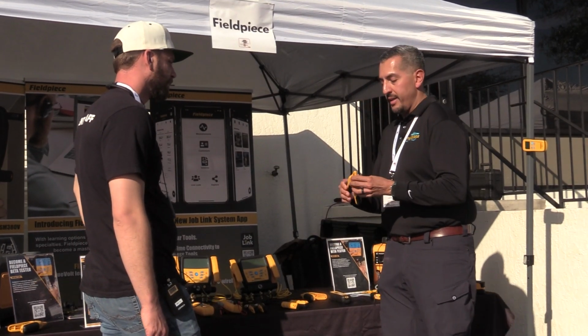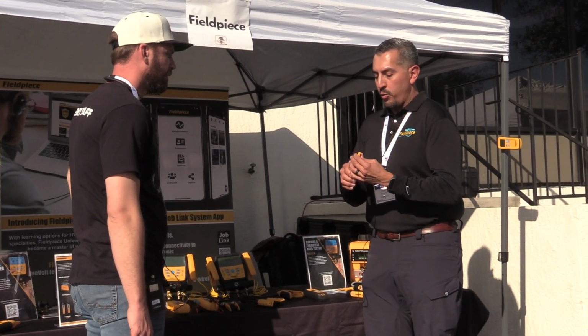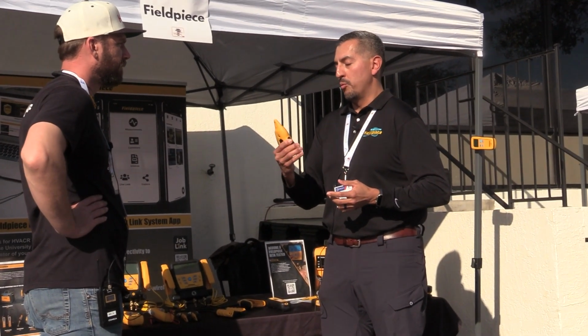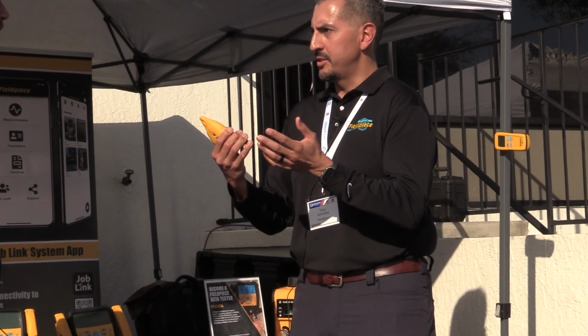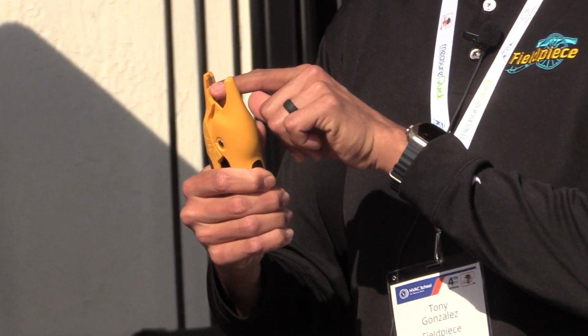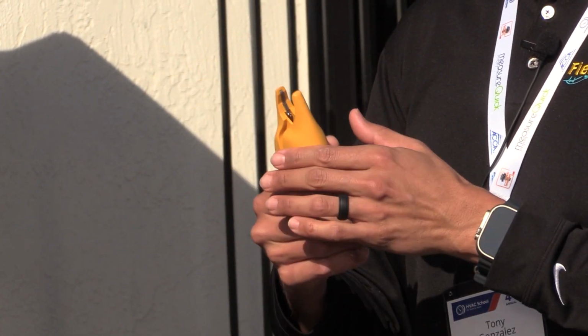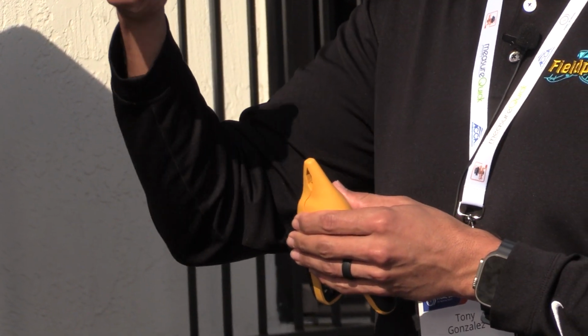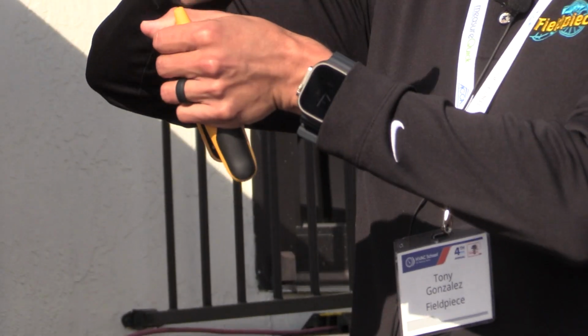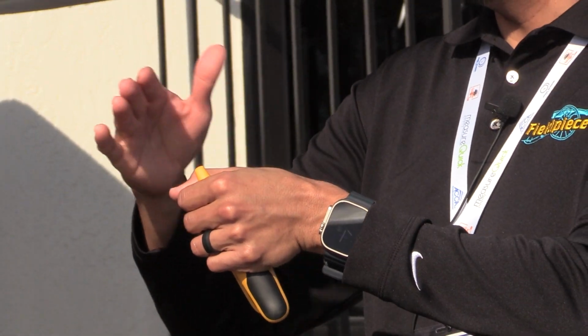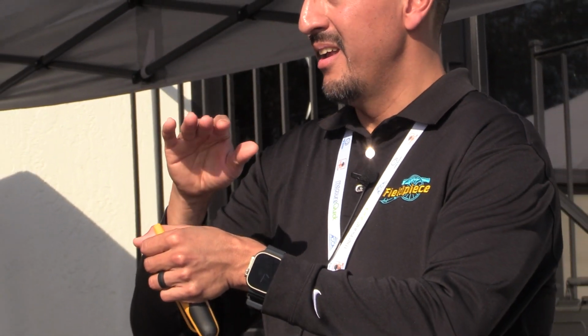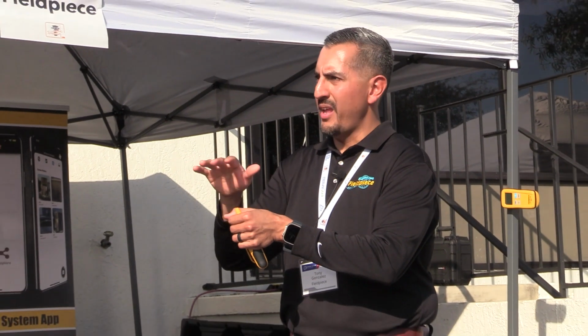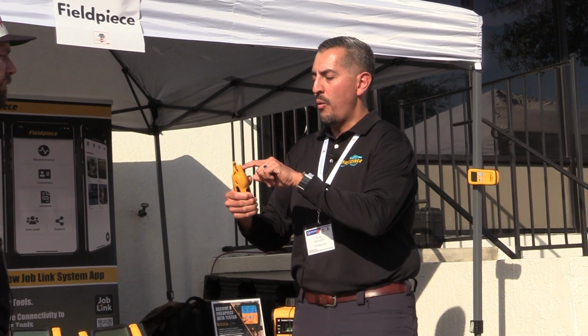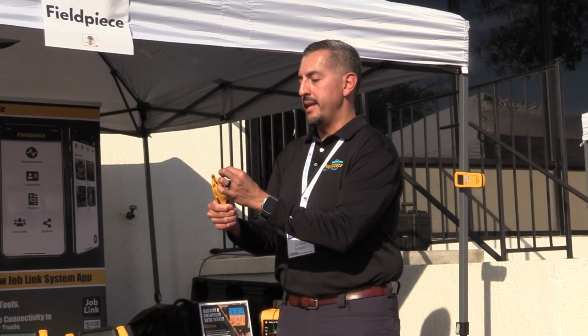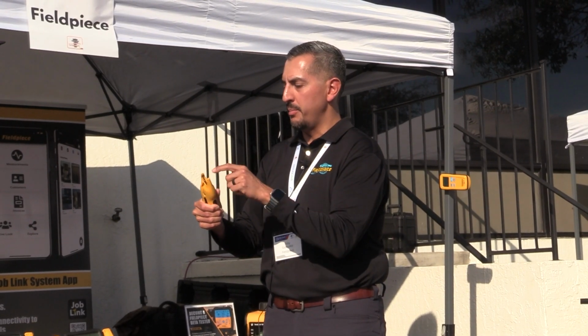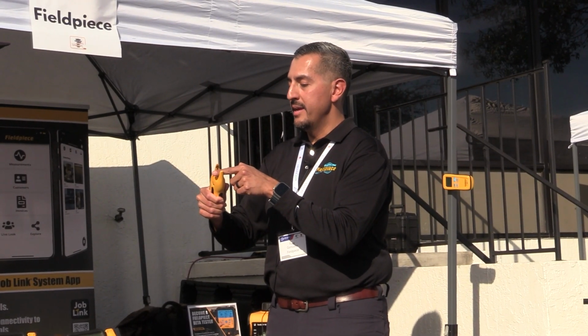One of the things that really makes the Job Link wireless pipe clamp great is our patented sensor technology called RapidRail. Unlike your traditional plate on a K-type thermocouple that goes onto the pipe and can be influenced by sunlight or moisture on the pipe—throwing off the accuracy of your temperature reading—RapidRail actually uses the conductivity of the copper pipe to become part of the temperature sensor.